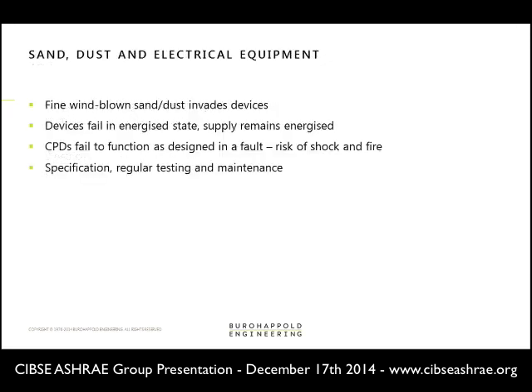The climate has a very big impact on the electrical equipment, so anything going outside has to be dustproof to prevent the failure of switchgear, control gear and machines. And the IP coding system is what we'll use. We wouldn't go below IP53 and generally like as high as IP64, 65. Wherever possible, we try and provide local shading to protect the electrical components. The surface temperatures of luminaires, for example, can get up as high as 80 degrees in the middle of summer. And it's just so high that any shading that can be provided really benefits the longevity of the installation.